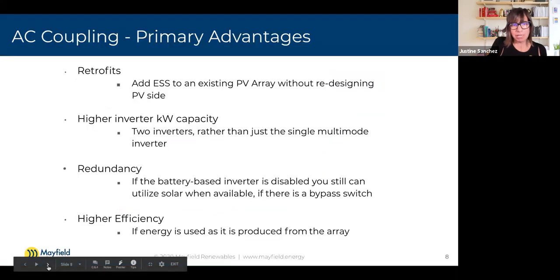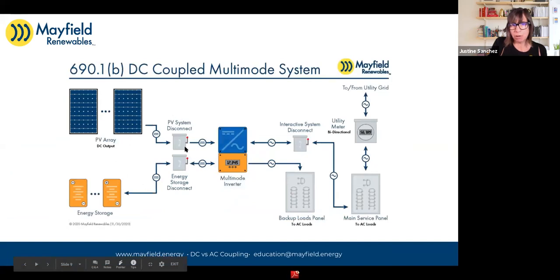So, but if you have a DC coupled system and you don't have that limiting piece of equipment between your PV array and your energy storage, you can utilize the full capacity of your array if it's available. And they're starting to design bigger systems with this in mind. Let's talk megawatts. And where you also have limitations when you get into interconnection limitations with larger systems, and even with smaller systems, on how much we're actually allowed to backfeed into the grid and into our bus bars and so on.